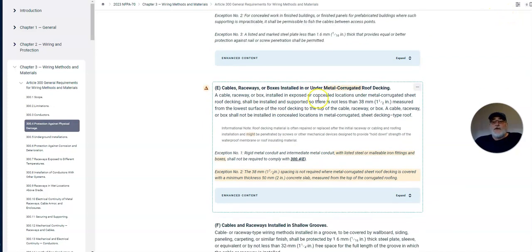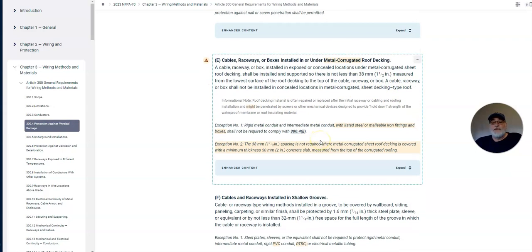Let's see. So that's where they said it shall be installed and supported so that it's not less than 1.5 inches measured from the lowest part of the roofing deck to the top of the cable, raceway, or box. The cable, raceway, or box shall not be installed in concealed locations in metal corrugated sheet decking type roofs. Okay, let's read this informative note. Roof decking materials are often repaired or replaced after the initial raceway or cabling installation and might be penetrated by screws or other mechanical devices designed to provide hold-down strength for the weatherproof membrane or the roofing material. That's the screws that I was talking about.